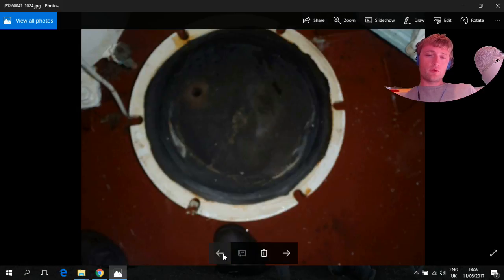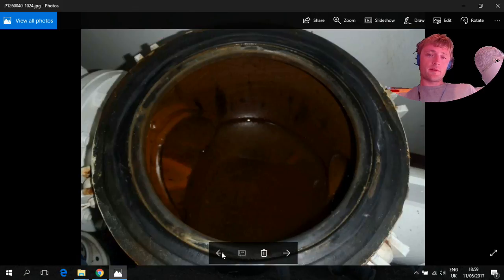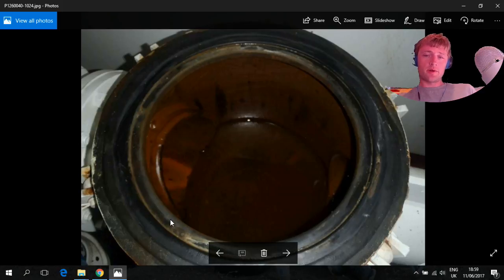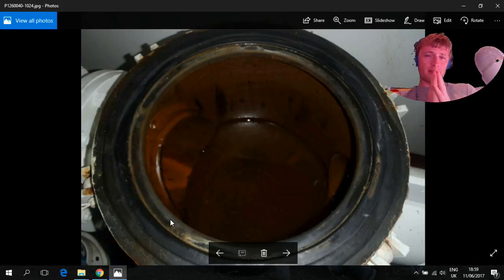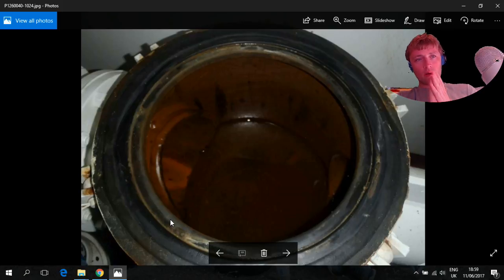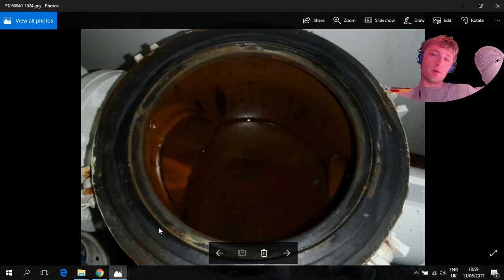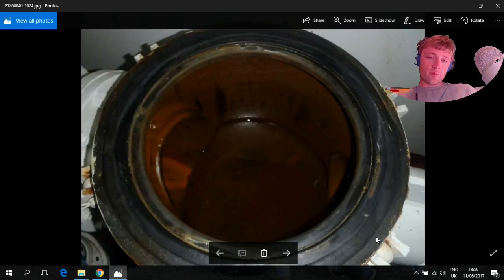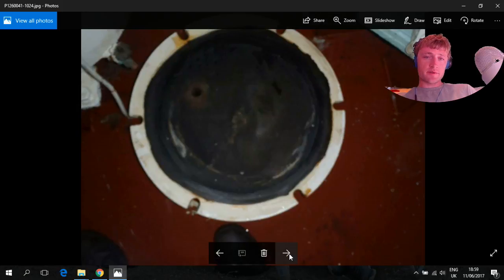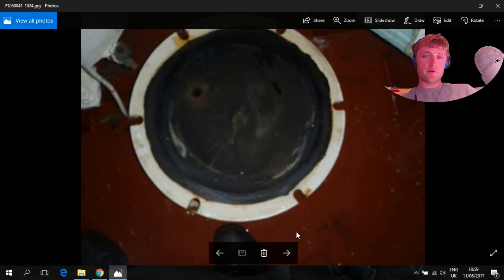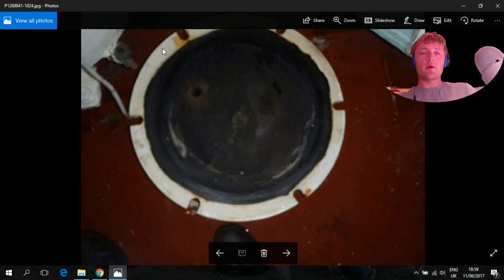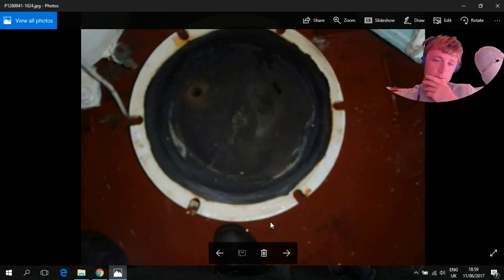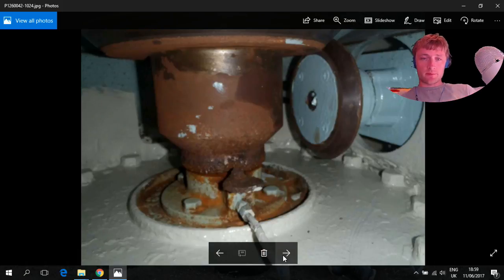Do not over-tight these covers if they have a rubber. If you over-tight your rubber, one day it will go out. This is for sure—it will break because down below the rubber there's metal surfaces. Also here, the cup is metal surface. As you can see, if there's over-tight through the ears, the rubber flows to the metal.